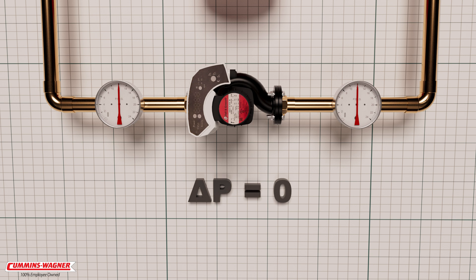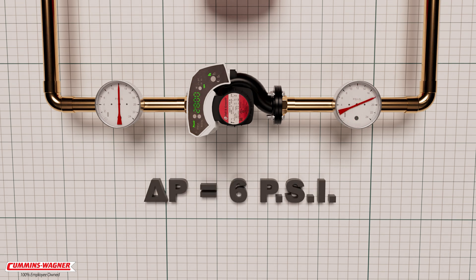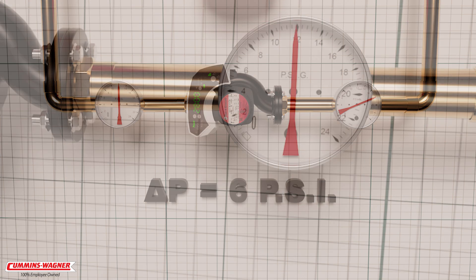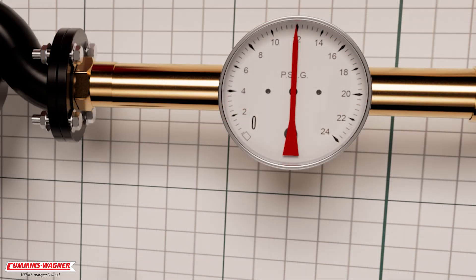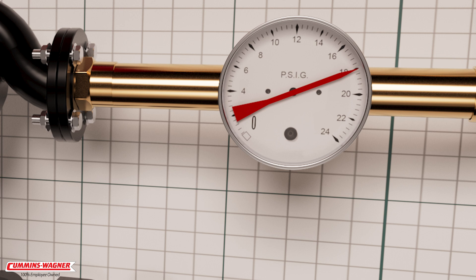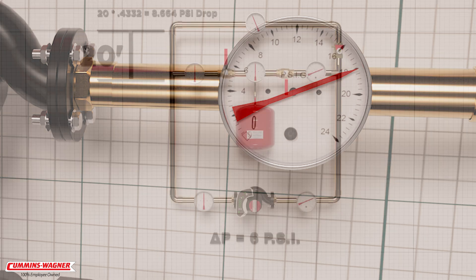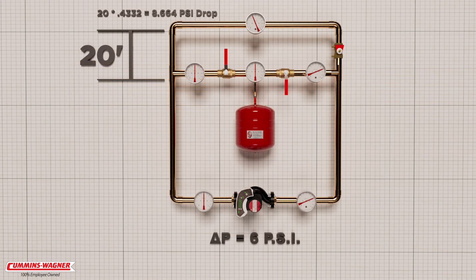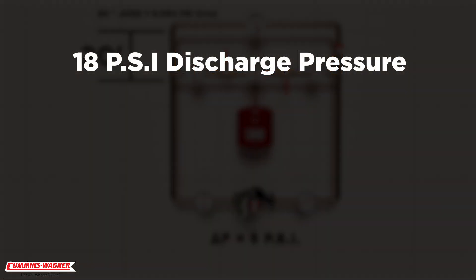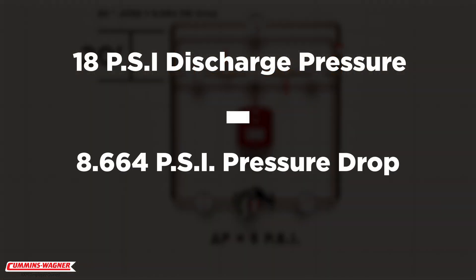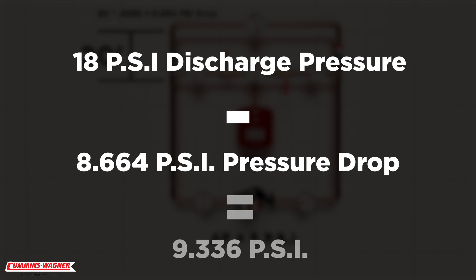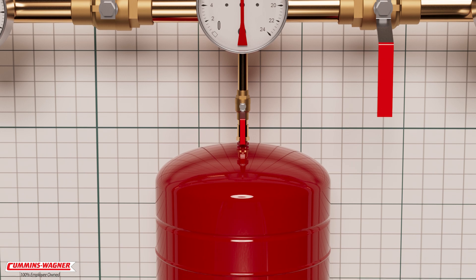It's important to remember that a circulator will always create a differential pressure when energized. In this example, our circulator generates a differential, or delta-P, of 6 psi. This increases the static pressure of 12 psi at the discharge of the circulator to a dynamic pressure of 18 psi. If we subtract the pressure required to get to the top of the system — 18 psi discharge minus 8 psi pressure drop — we are left with less than 10 psi at the top of our system.